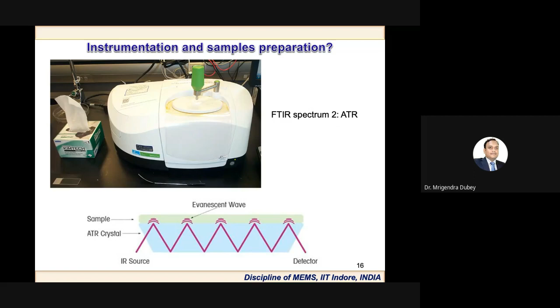So now the next question: how do we get an FTIR spectrum? As demonstrated here, we have this IR light source. In the first step, it will fall on the beam splitter. The beam will split into two parts. One will fall towards the sliding mirror, and another towards the fixed mirror. After that, collectively it will reflect and fall on the sample. It will pass through the sample, and whatever light is transmitted will be detected by the detector, and you will get the information in the form of spectra. So this is an overview of the simple setup of FTIR.